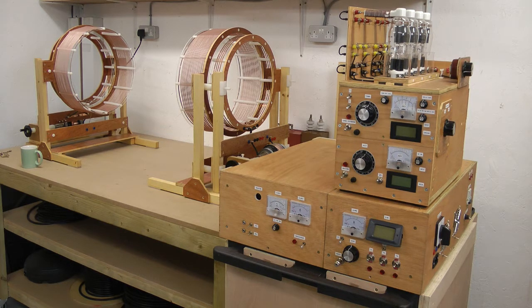It is quite sophisticated and has a whole different set of circuits in it. Obviously there's the high voltage transformers, there's a high voltage bridge rectifier, there's also a level shifter or a doubler in there, and there's also a high voltage discharge unit to allow you to discharge external capacitors, plus all of the necessary power control and safety features. So altogether quite an advanced supply.